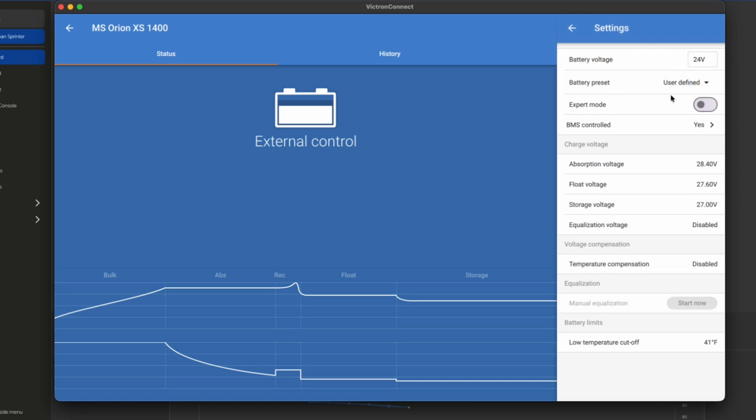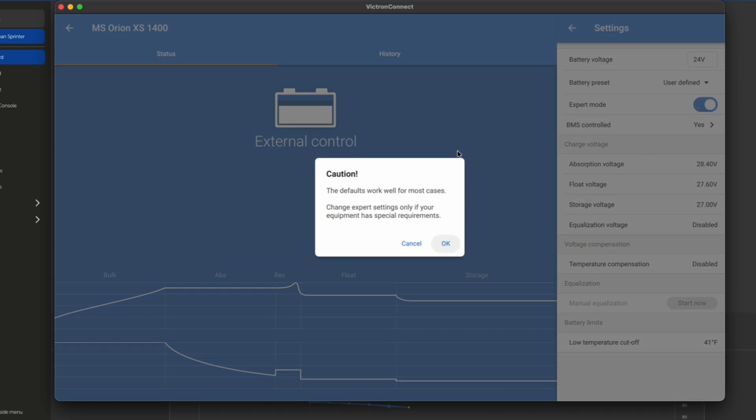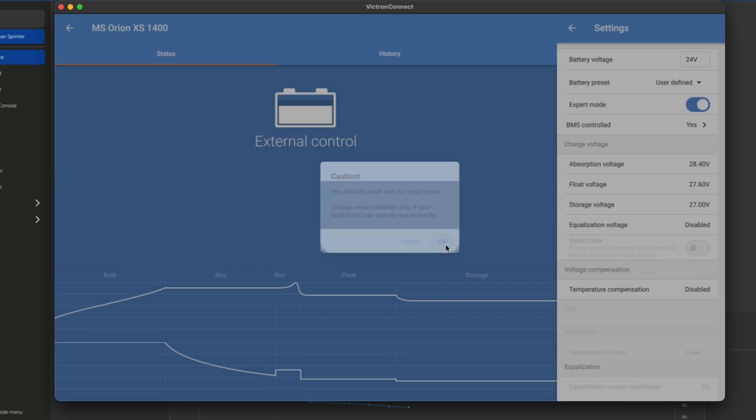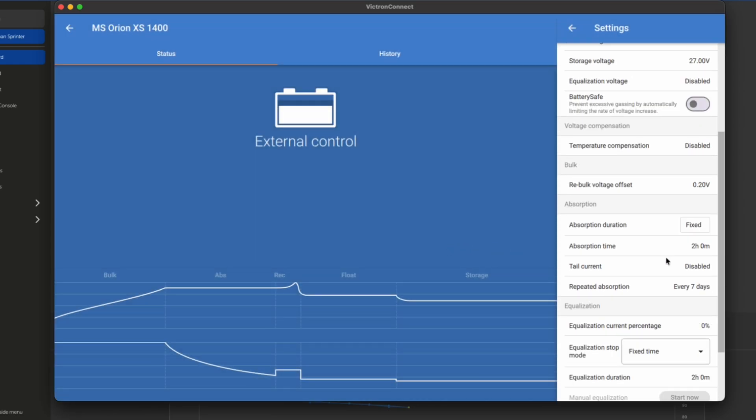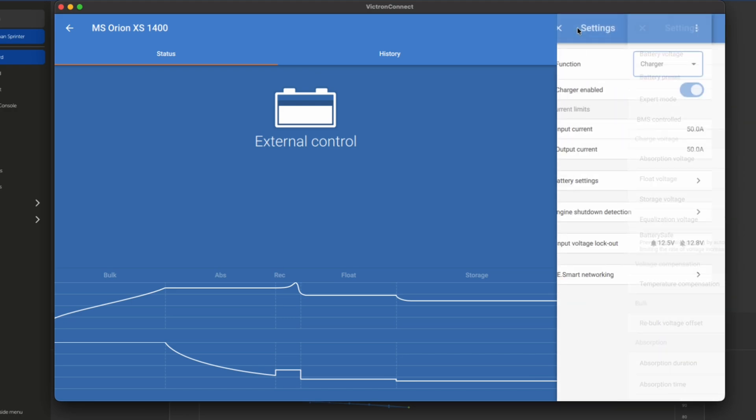Let's look at our battery settings. This is going to be our setup for charging our specific lithium battery. Jason has set this up to be ready to charge these Pylontech batteries. So he's got his absorption, float, storage voltages. Equalization is turned off because this is a lithium battery. This BMS controlled, this is something that automatically turns on when it's in a system with a GX device, like a Cerbo GX or a Ekrano GX or any other Venus operating system and it has a recognized BMS. It will pass this information along and turn on the BMS controlled. There are some further settings if you go into expert mode. Not something that is necessary very often. It gives us some additional settings for temperature compensation, rebulk settings, absorption. I'm not going to change any of this. If you need to do this, you probably know what you're doing already.